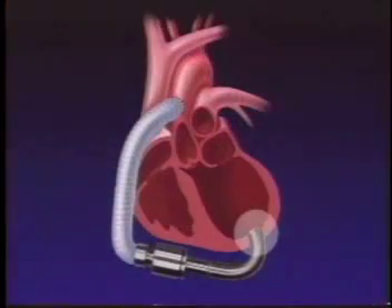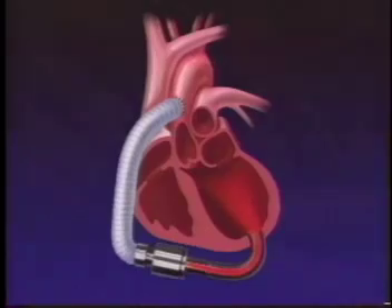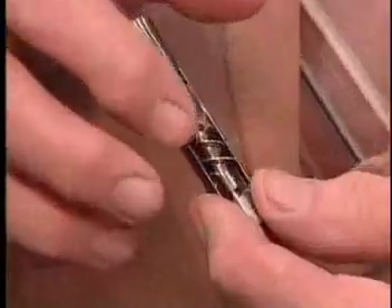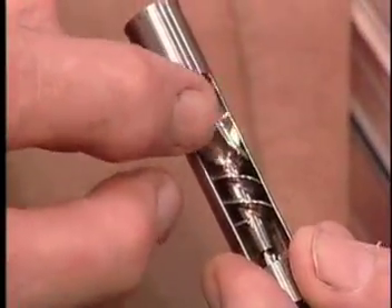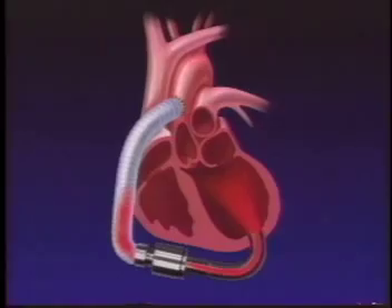The assist device essentially hooks to the left ventricle, and a small hose comes up and connects onto this end of the pump. The blood flows in here. These little blades sort of screw into the blood flow. It runs 10,000 revolutions a minute. The blood is rotating with the rotor. Then when it flows into the diffuser blades in the aft end of the pump, the blood's rotating motion is decelerated, discharged, and flows over into the descending aorta.